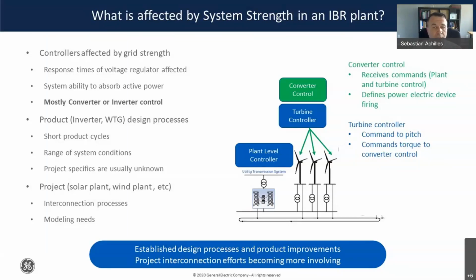As you can imagine, there is quite a bit of consideration for weak grid conditions. You can get to a particular level of weak grid in different ways, with different grid topologies where a load is located differently with respect to the utility grid and the plant, or where you have many plants close together. There are many ways of getting to the same system strength. So the system conditions considered in product design don't necessarily cover everything that's possible, but they try to cover the main characteristics of weak systems.